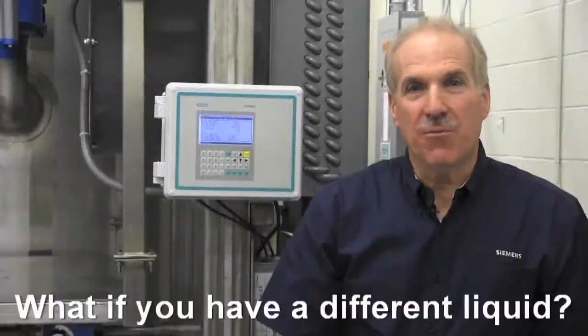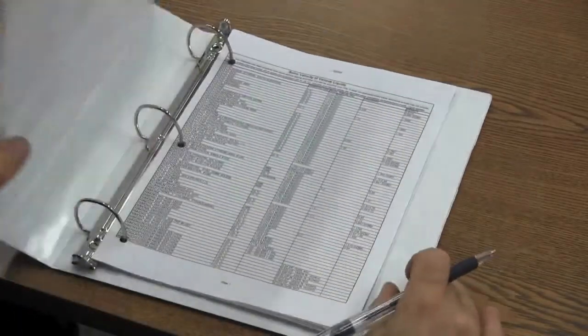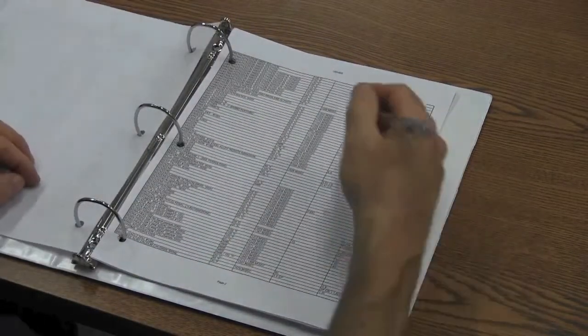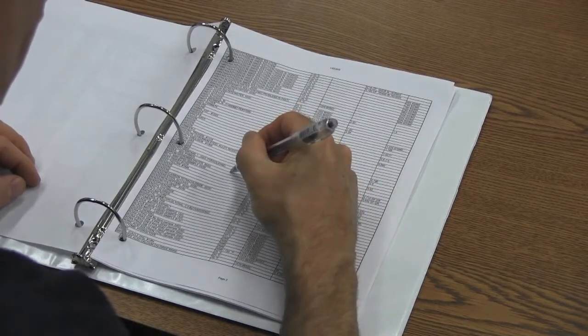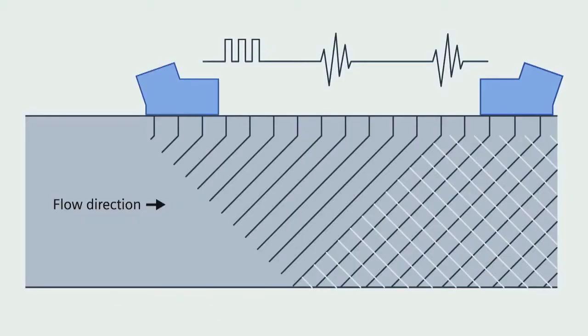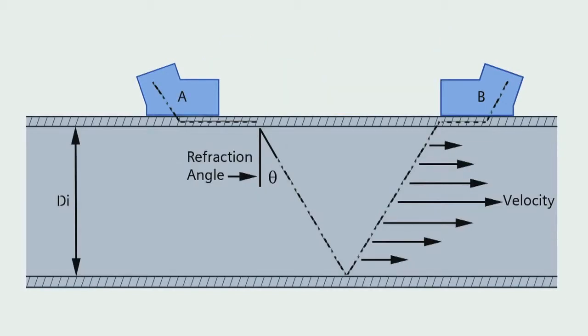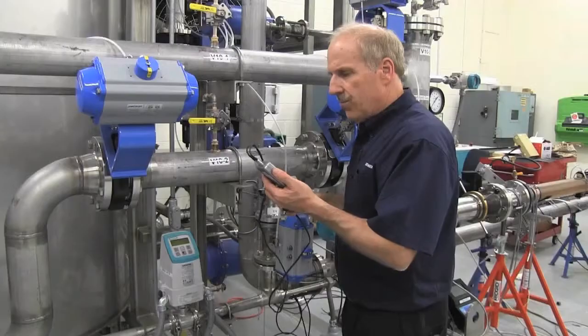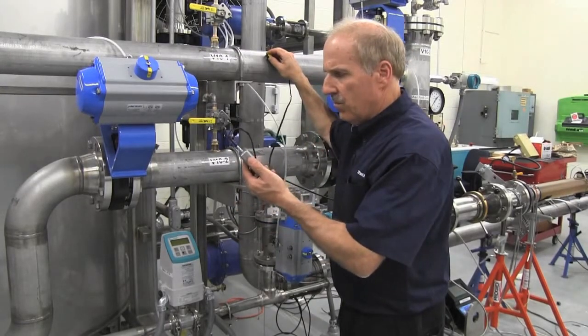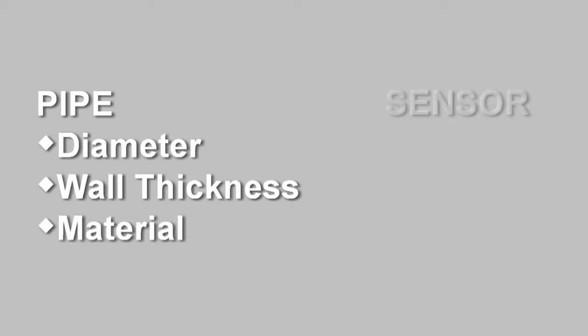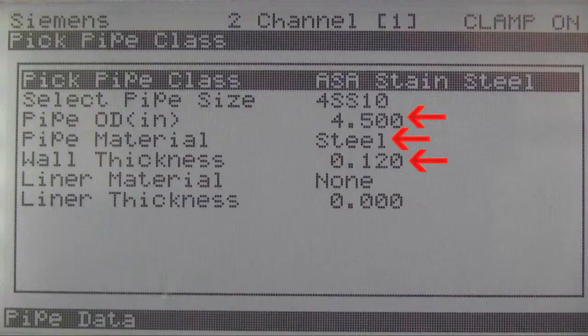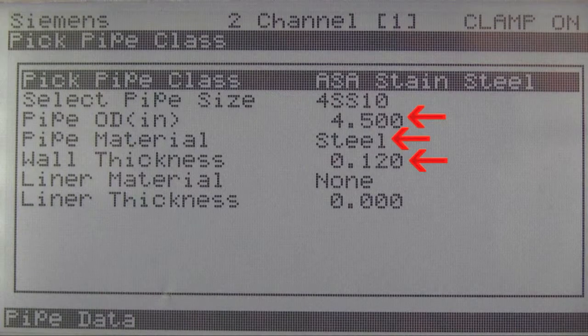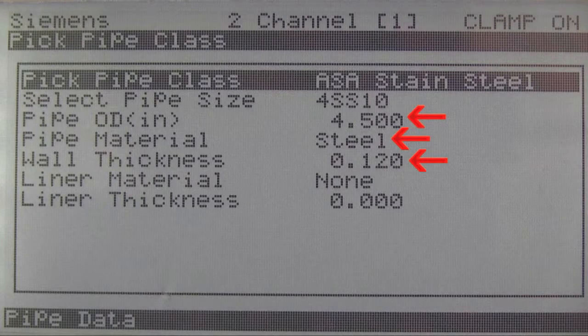What if you have a different liquid? Siemens also maintains a database of many common liquids. But you might have a liquid that does not appear in it. Don't worry though, it is quite easy to validate the measured value. VS is simply the result of a distance versus time computation. The flow meter can very precisely measure the time component and we can verify the preciseness of this measurement. That leaves the distance, or in other words, dimensional portion of the equation in question. Fortunately, the dimensional values are something you have complete control over. The dimensions relate to the pipe diameter, wall thickness, and material, plus the sensor type, size, and spacing. Therefore, by ensuring the accuracy of these values when you program the meter, you eliminate any possible source of dimensional error.